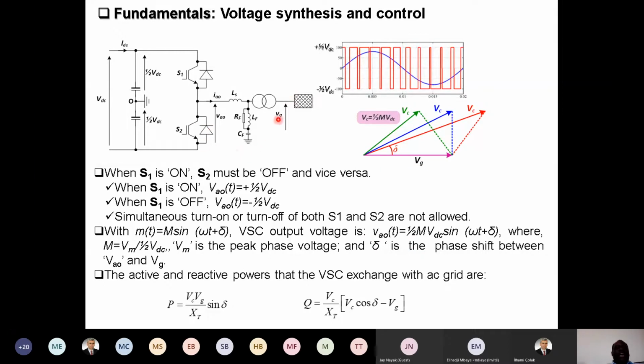And when we operate in the grid, we actually control power by manipulating this modulation index and this angle, or the angle of this voltage relative to the grid voltage, as we have here. So this is the first diagram that depicts how the VSC controls active or reactive power. If we define the grid as a reference, and we control the converter voltage vector to lead the grid voltage, the power flow will be from the converter toward the grid. If the vector lags the grid voltage, the power flow will be from the grid toward the converter.